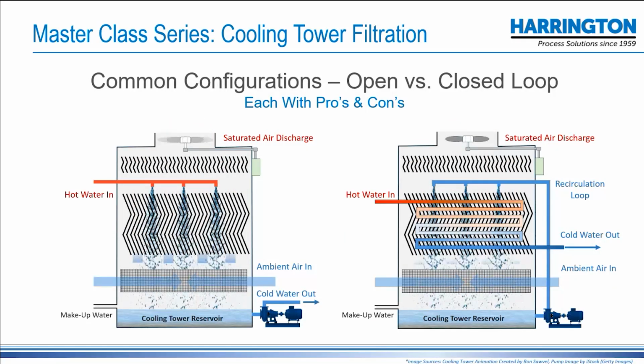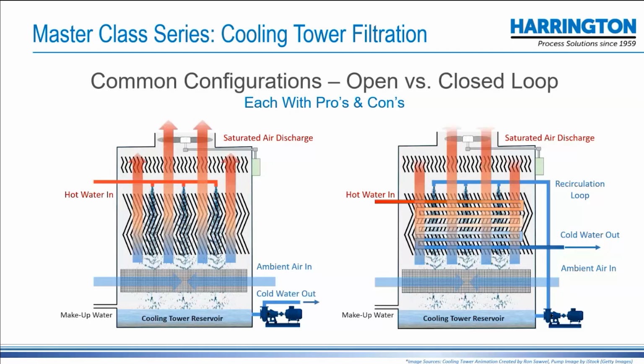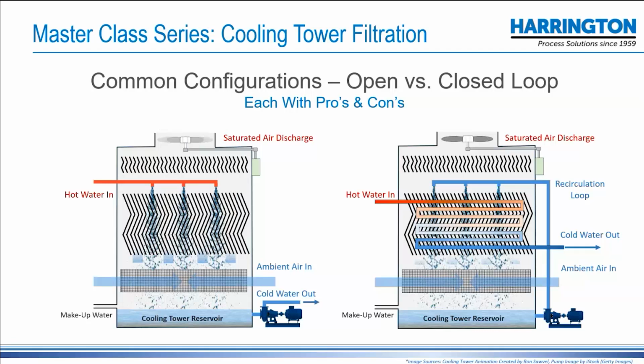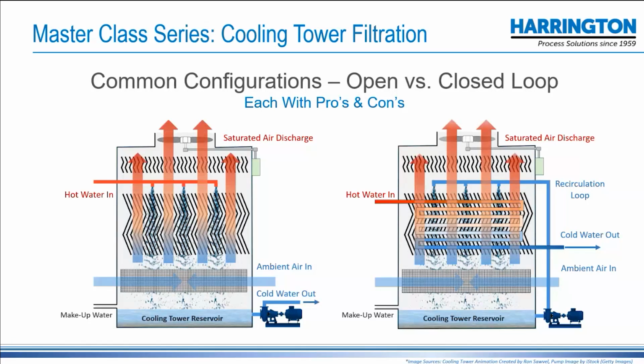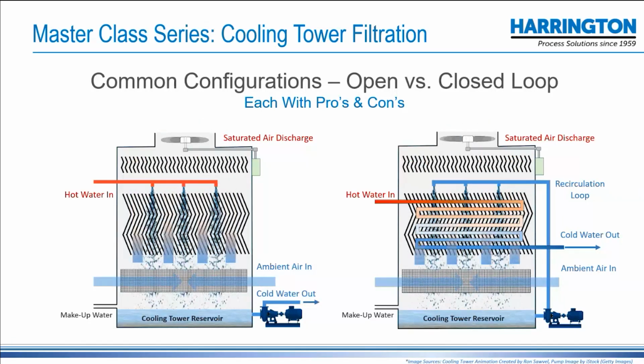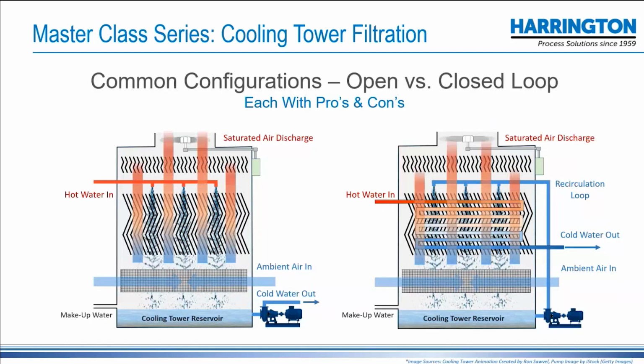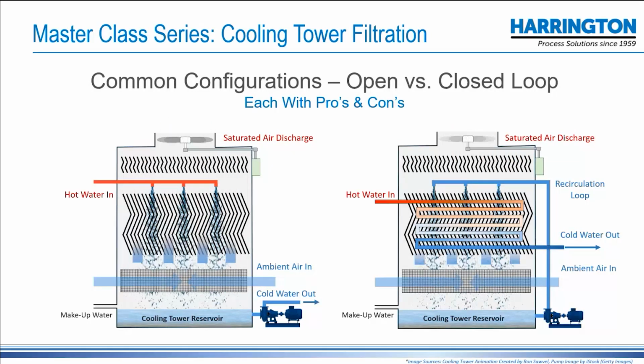The big problem with, or feature, I guess you would say, of cooling towers is that they draw massive amounts of ambient air in, and that air is saturated with dust. Depending on where you live, you may be bombarded with dust and have to change filters in your air conditioner quite often because the ambient air is dust laden. Well, this just goes straight into the cooling tower and drops down with the water into the cooling tower reservoir and collects there. And it eventually will create a sludge layer at the bottom of that cooling tower reservoir. And there'll be more on that in a bit.